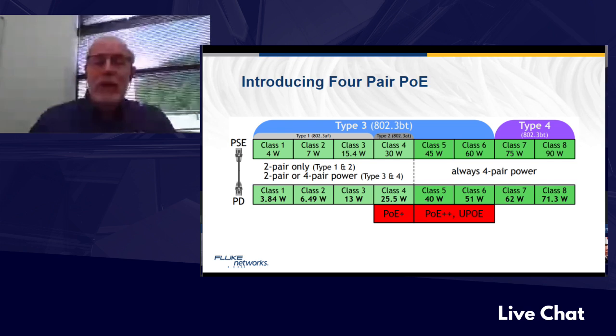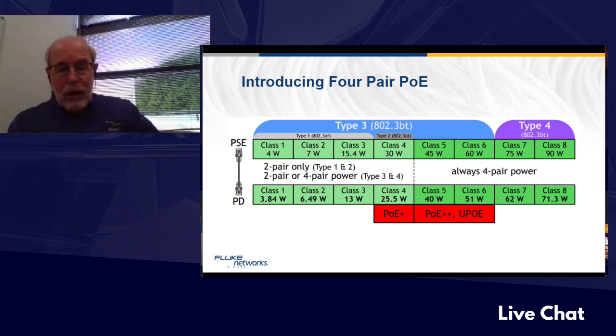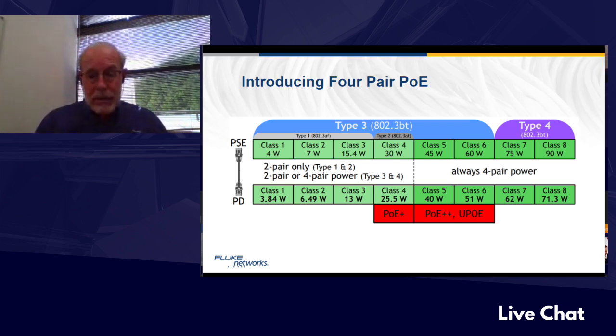With four-pair PoE, you've got these different classes, different power levels. The standard talks about the power level delivered by the switch. So for class 5, you've got a certain number of watts at the switch, but because you may lose some power over the cabling, the device at the far end should only expect to get 40 watts. It may get more depending on how good your cable is, and we'll talk about cabling in a few minutes. That allowance just makes sure everything works. Everything class 5 and above is 4-pair power, all described by the 802.3BT standard.